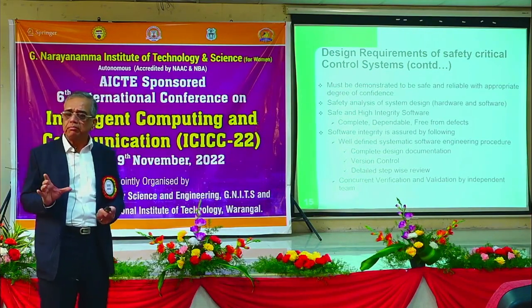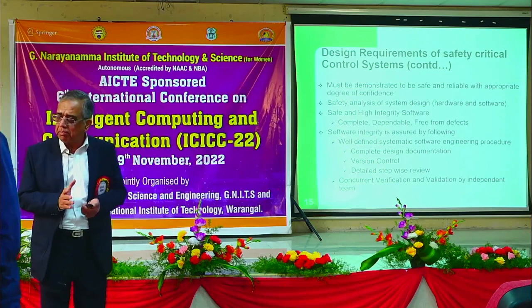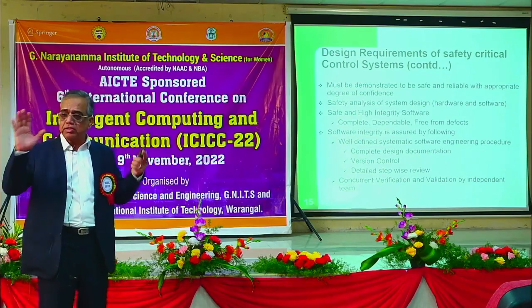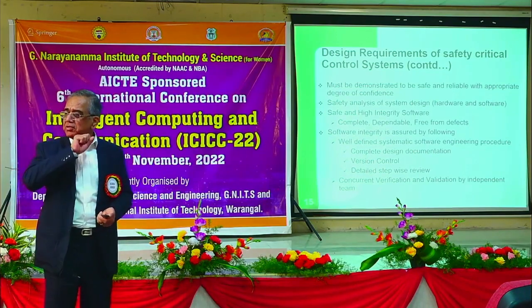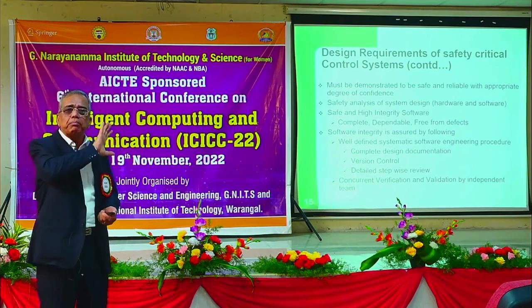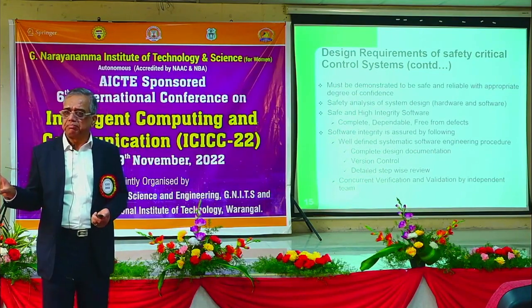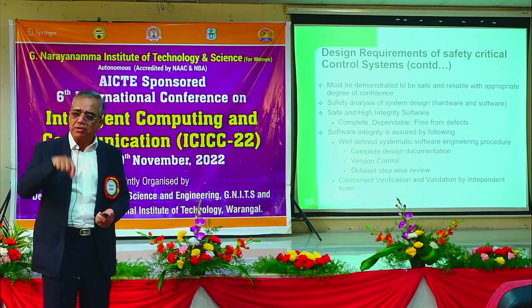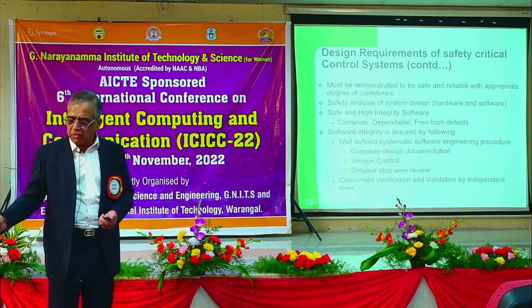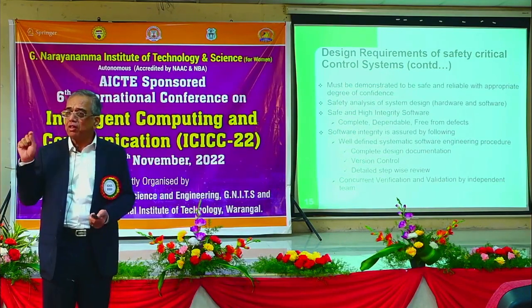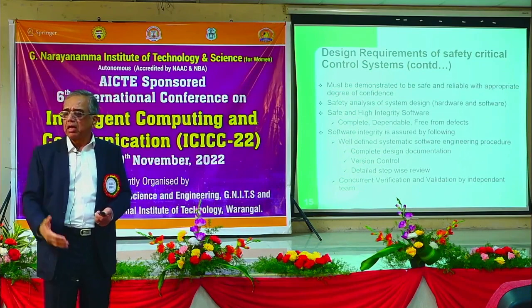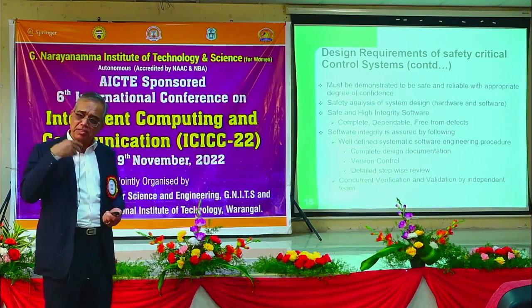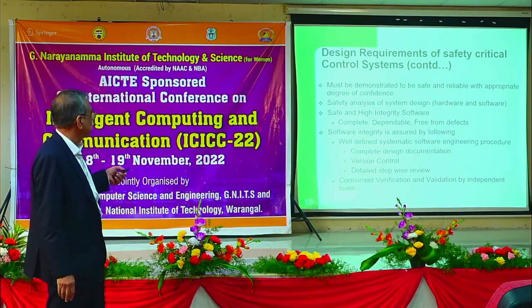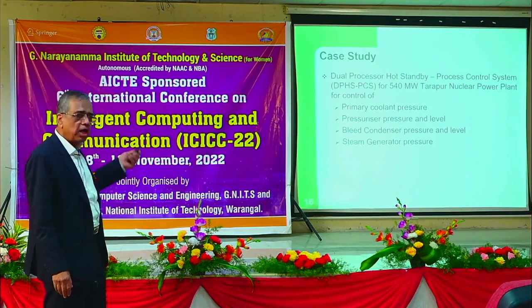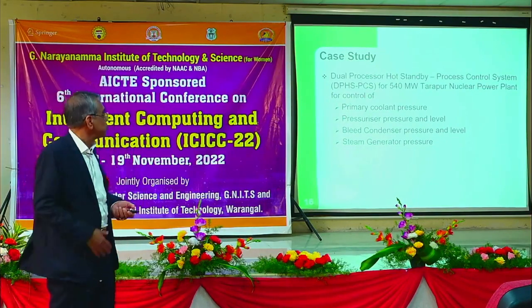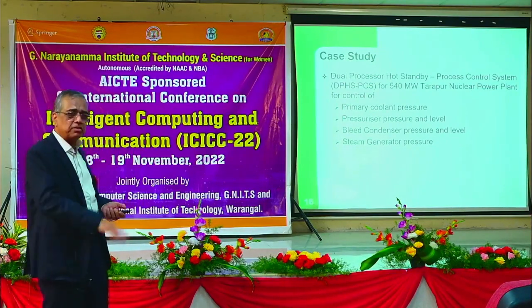What is validation? When the software is completed, we have to make a full scale prototype system on which the software is loaded, and then perform all the functions, including failures - if power supply fails, what happens, if this fails, what happens, and so on. A complete test report has to be generated, which again needs to be presented to the AERB. Now I will take one case study which we have designed for one of the systems.